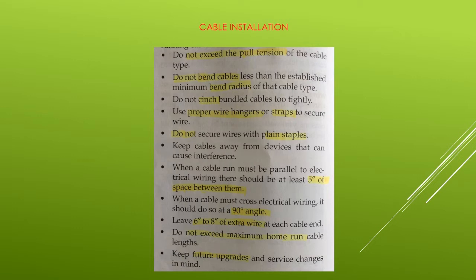Cable installation. These rules should be followed when running cable. Do not exceed the pull tension of the cable type. Do not bend cables less than the established minimum bend radius of that cable type. Do not cinch bundled cables too tightly. Use proper wire hangers or straps to secure wire. Do not secure wires with plain staples.